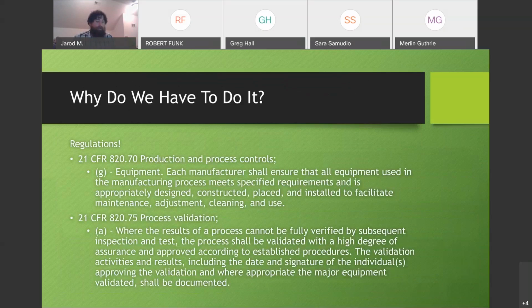So why do we have to do it? Within the medical device industry, it is required by regulations. For instance, FDA 21 CFR 820.70, production and process controls. Specifically, subsection G states, for equipment, that each manufacturer shall ensure that all equipment used in the manufacturing process meets the specified requirements and is appropriately designed, constructed, placed, and installed to facilitate maintenance, adjustment, cleaning, and use. So very high level, not defining what those requirements are, but just saying that manufacturers shall ensure that the equipment meets the specific needs appropriately.